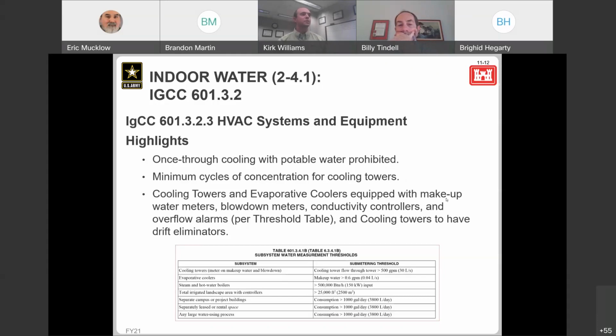Next one is minimum cycles of concentration for cooling towers. In simple terms, this is the number of times your cooling tower recirculates the water before it blows it down. The criteria has different settings based on your makeup water hardness, and the number of cycles ranges from 3.5 to 5 depending on your makeup water. Personally, I've seen a lot of poor examples of this. I've come across multiple cooling towers that are doing one cycle of concentration, and you go through a lot of water and a lot of chemicals. It can make life a lot better if you have things set up correctly. So that's a real simple operations item, checking your cycles of concentration.